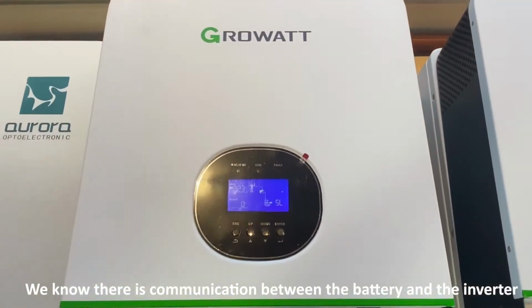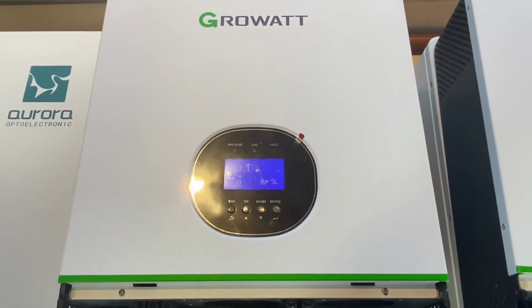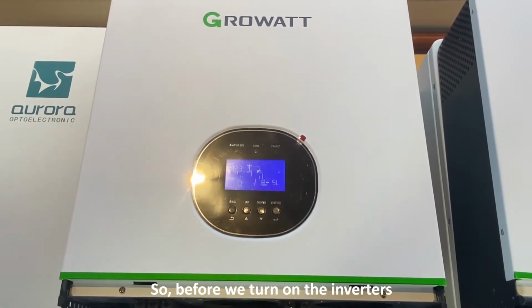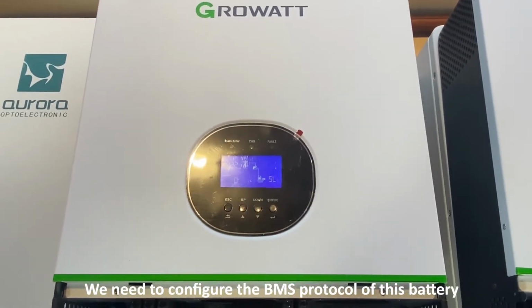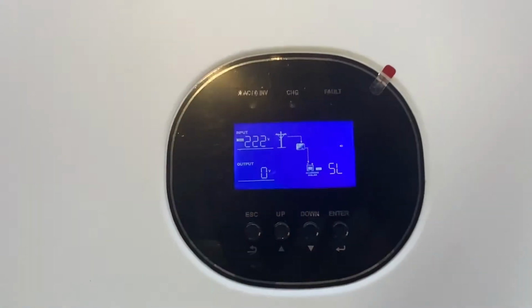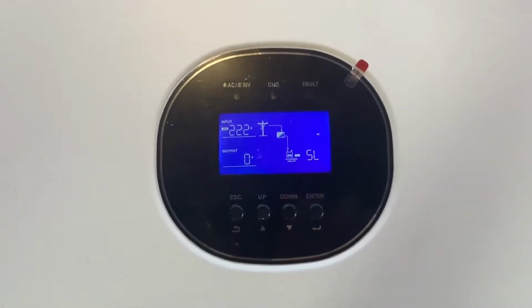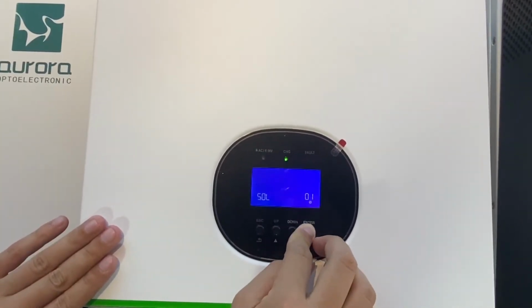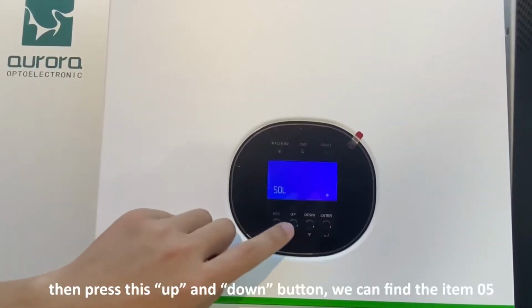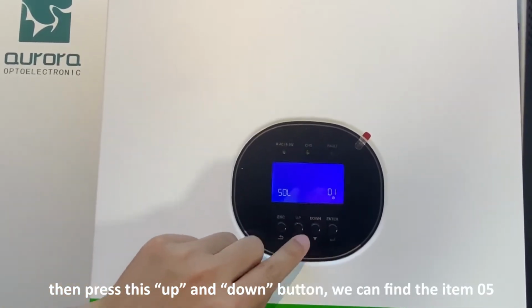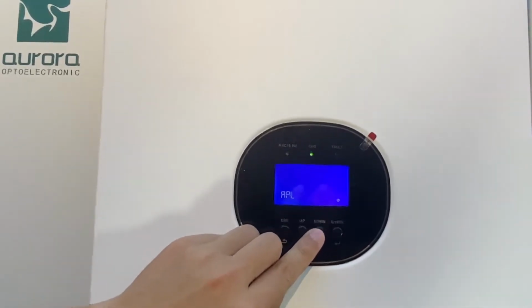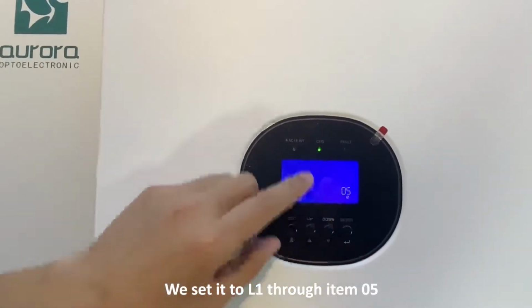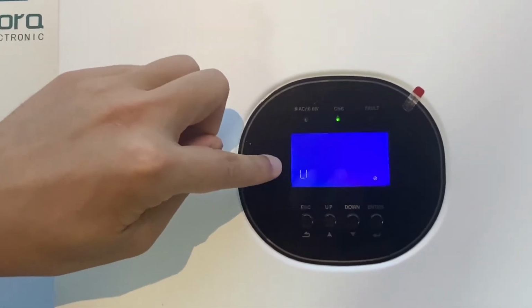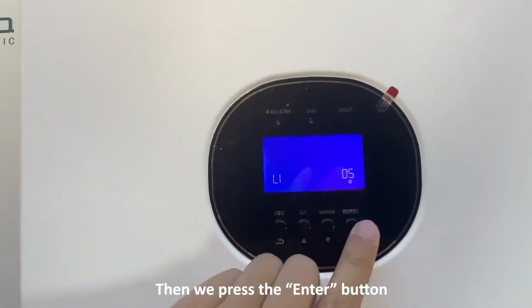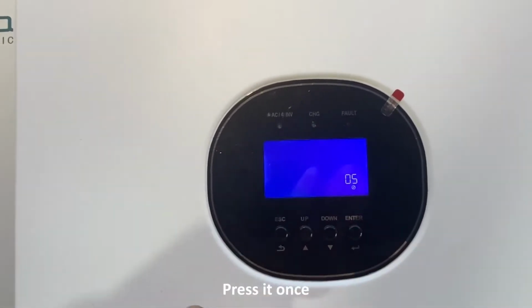We know there's communication between the battery and the inverter. So before we turn on the inverters, we need to configure the BMS protocol of this battery. Parallels also need to be confirmed. First of all, we need to long press the enter button to enter the setting menu, then press the up and down buttons. We can find item 05. We set it to L1 through item 05. Then we press the enter button once.